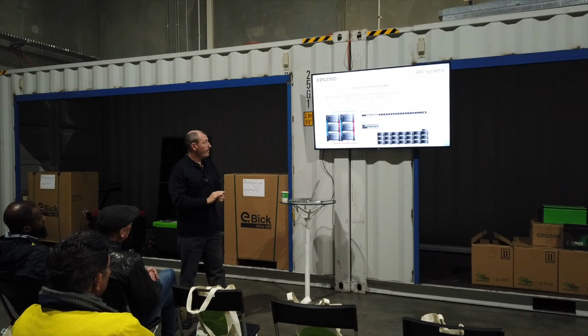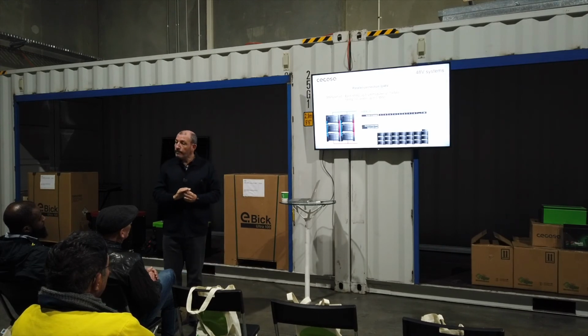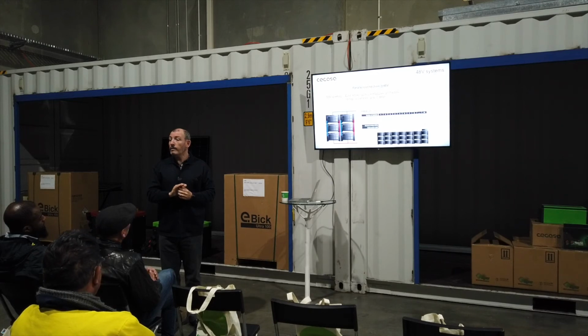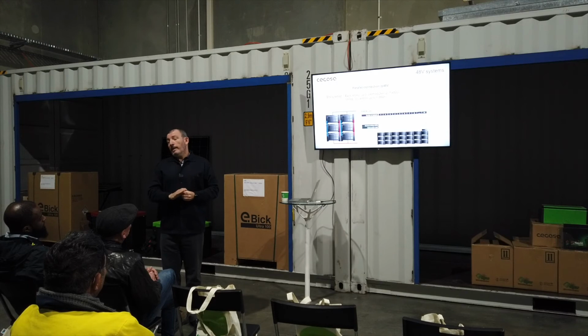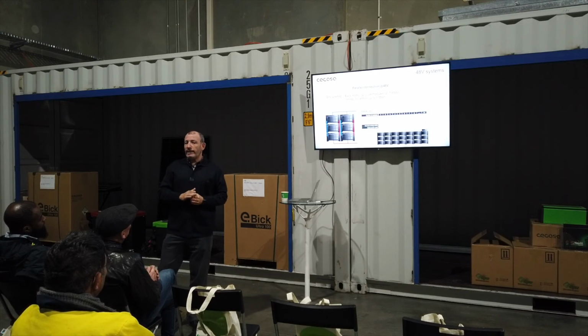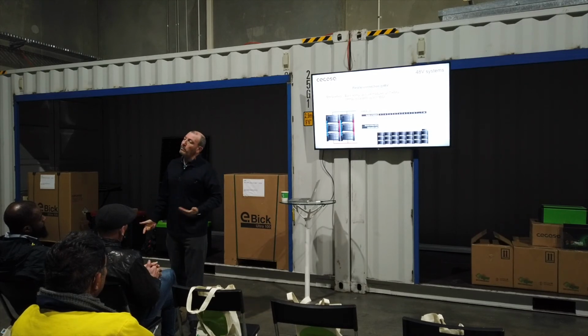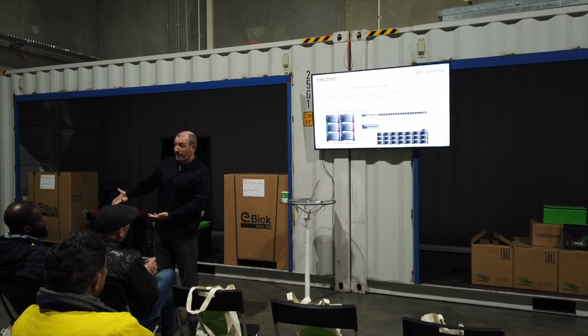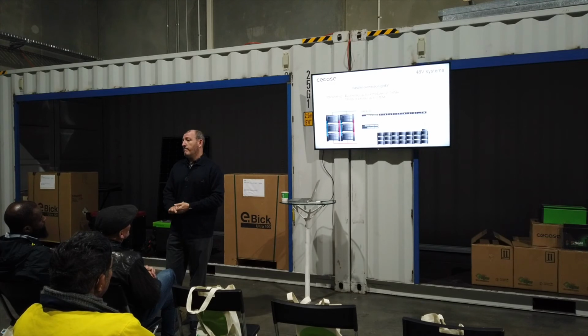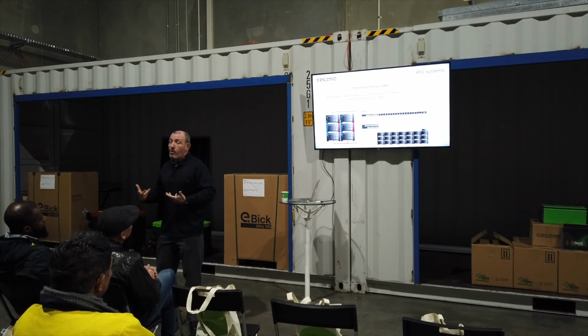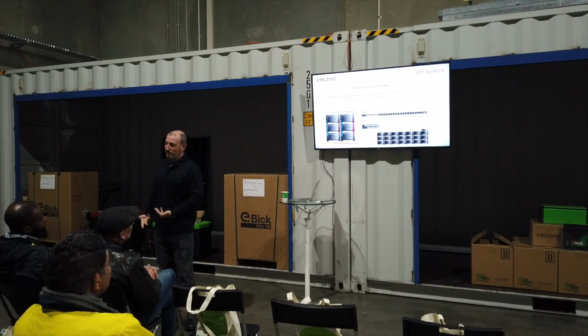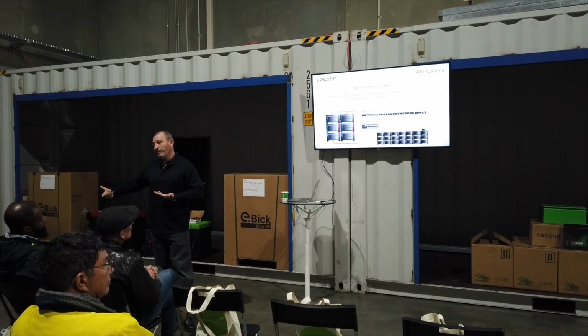Earlier you mentioned that for now you only need 3, and later if you want to expand you can add more - but you cannot connect the existing with the new one because they have different lifespans already. Good point, but if you find a way to equilibrate them, it's possible. Of course, if the system is 10 years old you might have a lot of trouble, but if it's from last year, you can keep balancing them. It's not so much the age, but how much the battery has been used and the level of degradation.